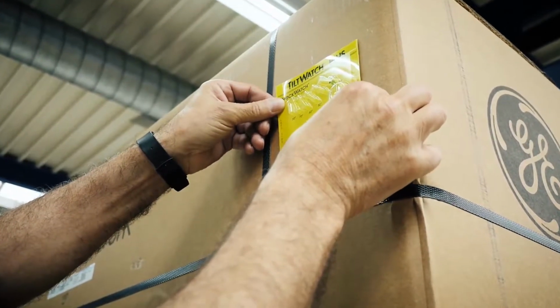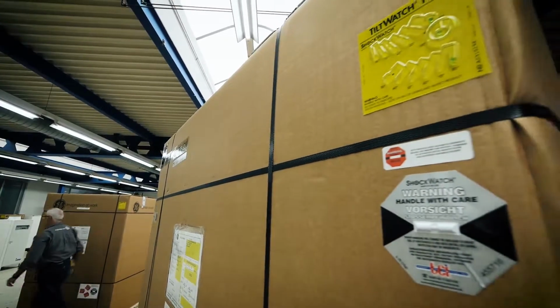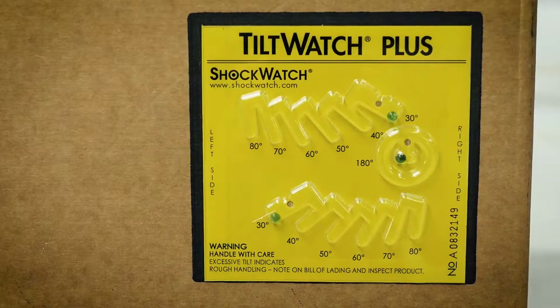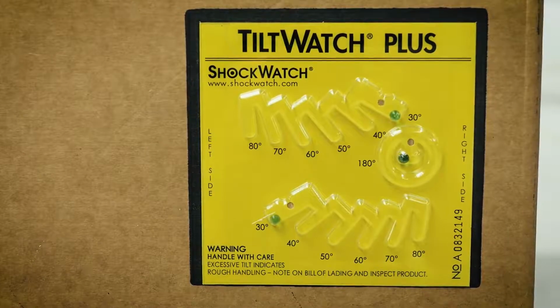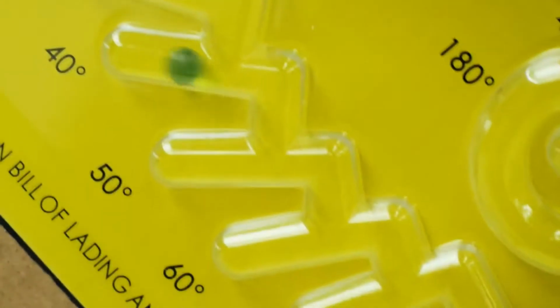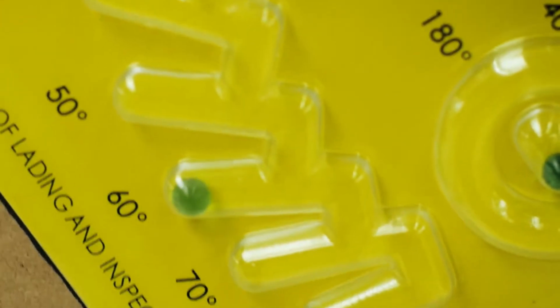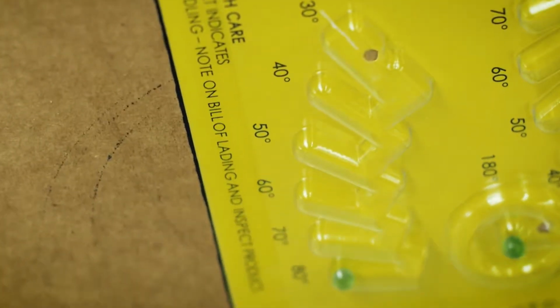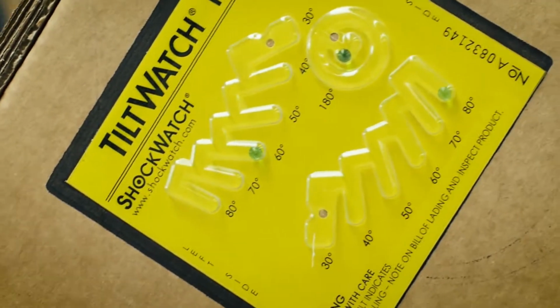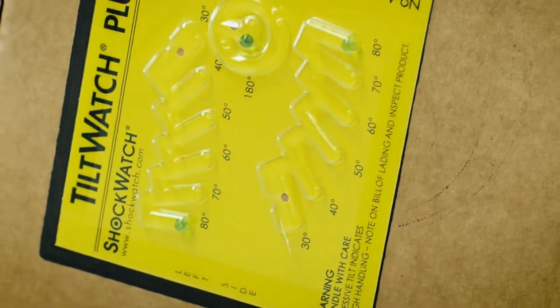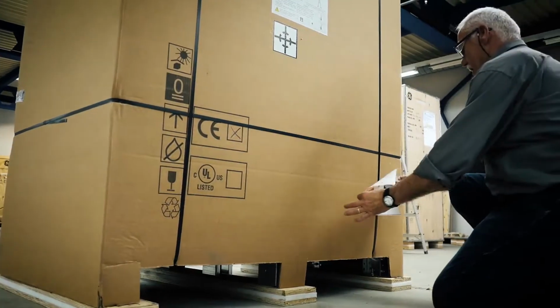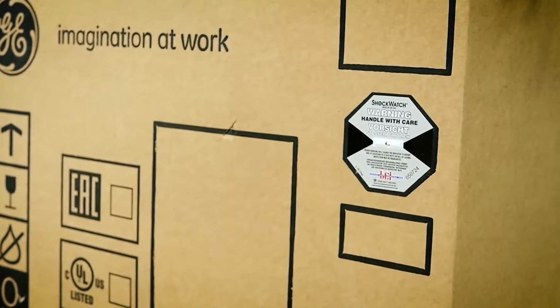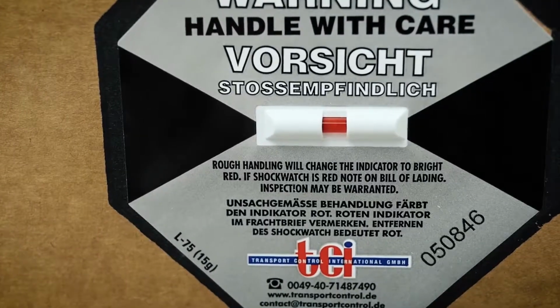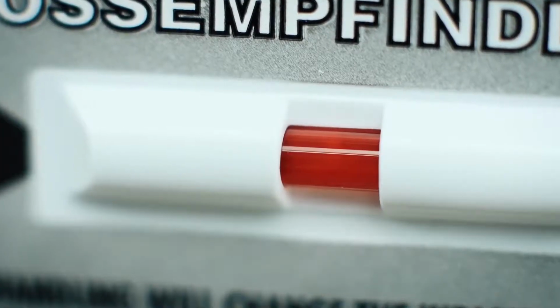To assure producers and customers that nothing happened to the UPS during transportation, there's a special sticker on the UPS with a small ball inside. When tilted, the ball starts rolling, and it's clear that the UPS was transported improperly. In addition, every box is labeled with a dye capsule. If the UPS was subjected to frequent and heavy shaking during transportation, the capsule breaks and the dye stains the sticker red.